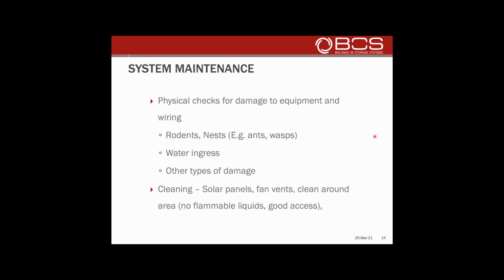If water's got into any part of the system - into the cabling, piping, ductwork - or other types of damage, like someone drove a car into the batteries, or swung a hammer in the wrong spot and smashed something. There's all sorts of ways equipment can get damaged, and you don't always know about it, as someone might not want to tell you they accidentally hit the system with a hammer.